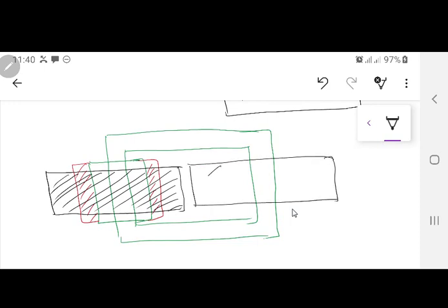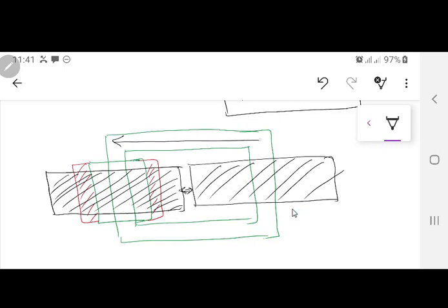then the distance between the two has to be some threshold value. You cannot keep them absolutely close. Why? Because that is A phase, that is B phase. Between the two phases also there is a line to line voltage. So when this distance is kept, then afterwards you can know, okay, this much is the yoke size. This is the actual design technique involved whenever you are designing a distribution transformer of something 200 kVA to something 500 or 2500 kVA. In this, you have to do the tank design at the very end.